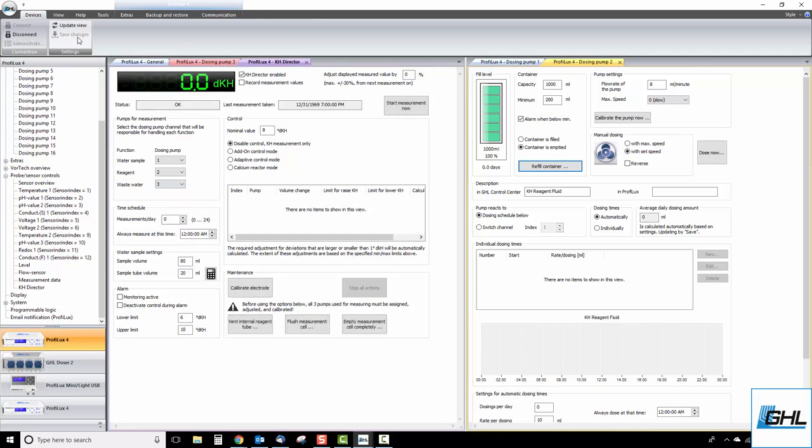The next step will be to set up your water sample settings. In the sample volume field, select the water sample size you want the KH director to use for each test. Keep in mind, the larger the water sample, the greater the accuracy.